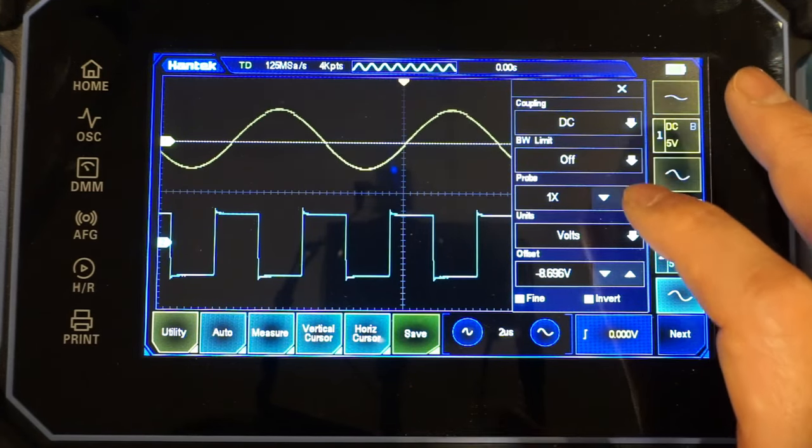For that, I'm using my Fluke 732A voltage standard up there. You can see I have already powered it up for a while and it's right now outputting a 1 volt signal. And we can see we are able to measure that with no problem. So let me just quickly cycle through the voltage range here. So let's go to 2 volts, 3, 4, and you can see that's because it's a 4 thousand counts meter. Now we dropped one digit here. 5, 6, and the measurement is relatively quick. 7, 8, 9, 10. No problem.